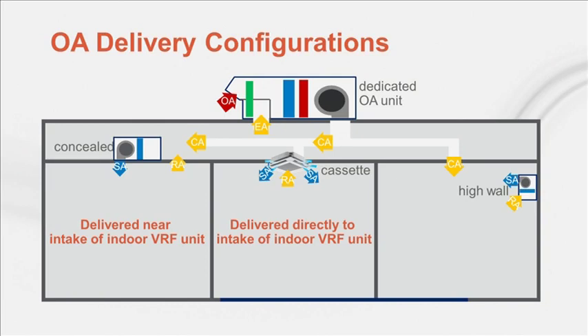The center zone shows the outdoor air ducted directly to the indoor terminal. This diagram shows a cassette-style unit, which often includes a knockout for connecting the outdoor air duct to it. But this approach could also be used with a concealed unit if the outdoor air duct connects to a mixing box or a short section of ductwork mounted to the inlet. Finally, the right-hand zone shows the outdoor air delivered directly to the zone. In this case, a high-wall VRF terminal is mounted in the space, but this configuration could be used with any style of indoor unit. Let's take a moment to discuss the advantages and challenges of each approach.